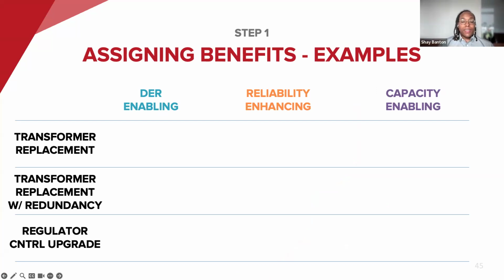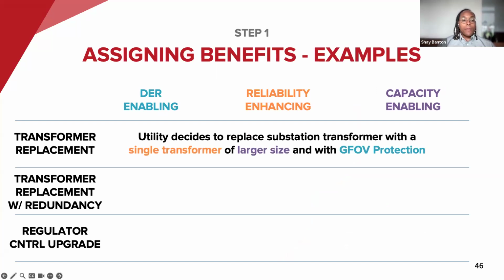As an example, a transformer replacement: the utility decides to replace a substation transformer, this time a single transformer, and increase its size. Because penetration has been increasing in the area, they also install ground fault over voltage protection, referred to as 3V0, to ensure backfeeding of that transformer can occur without being detrimental to the health of the system.